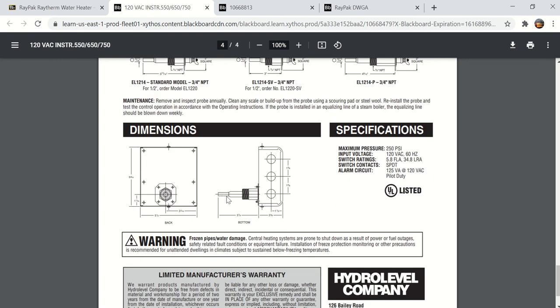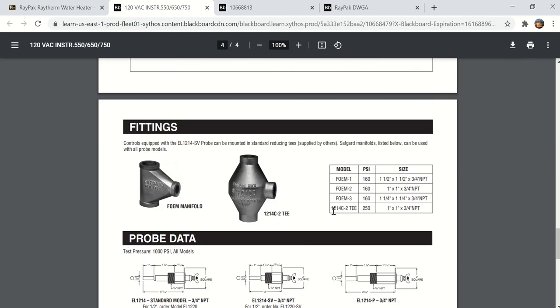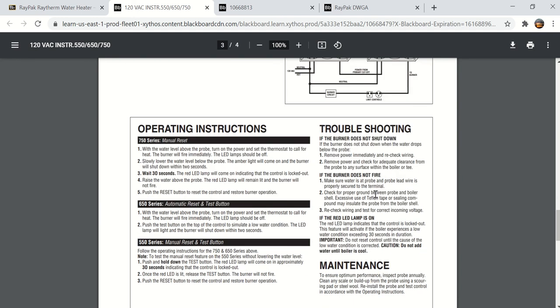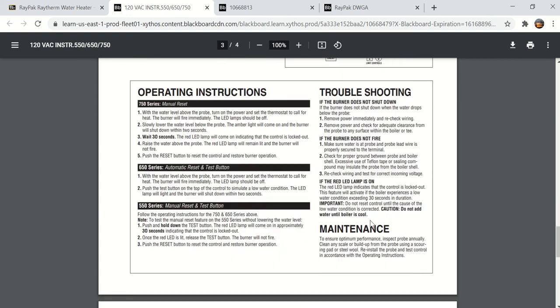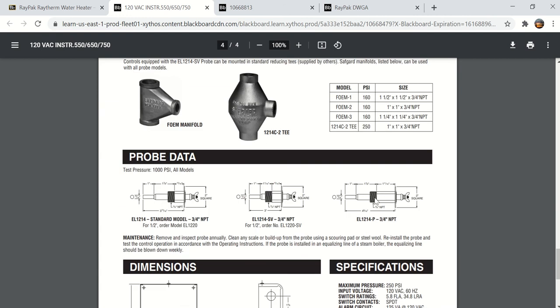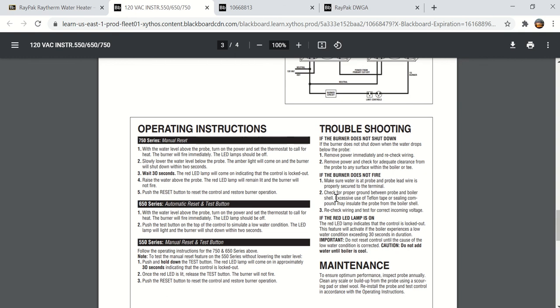This talks about the dimensions and the probe, and a little bit about troubleshooting if you lose power. Here this is pretty important on installing that probe. This probe here, you screw it into the side of the boiler or into a fitting, and it tells you that an excessive amount of Teflon tape can keep it from reading to ground. So it's pretty important when you put Teflon tape on there, don't overdo it, and make sure that when you screw it in, it does make a good connection. And here it talks about the lights and the 30-second duration and time for the manual reset to take effect.